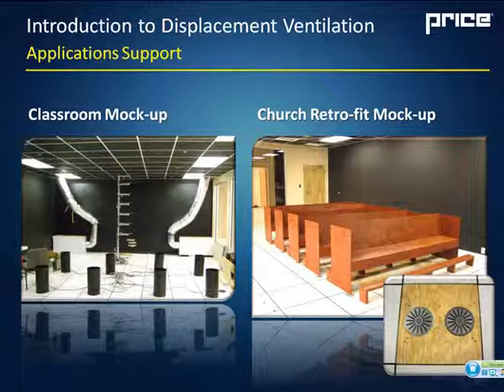So a couple different mock-ups we've done here. We have a classroom mock-up here where each of those cylinders is representing an ASHRAE standard person or child. And you see the displacement diffusers at the back of the classroom and the data tree, which is collecting results throughout the room. We did a church retrofit mock-up here, just some examples where we see underfloor diffusers placed right underneath the pews, and the owner wanted to see that the system was going to be comfortable, even with the diffusers only several inches away from the people's feet or from their legs.